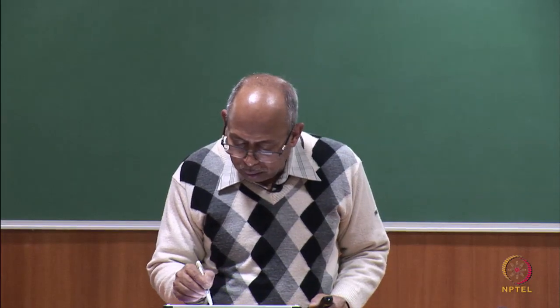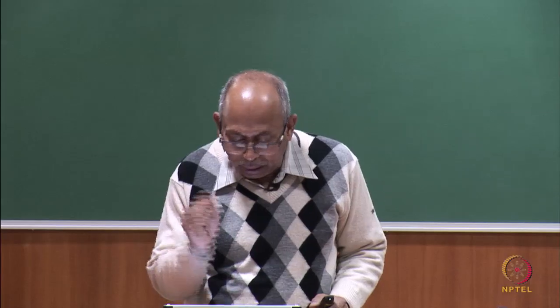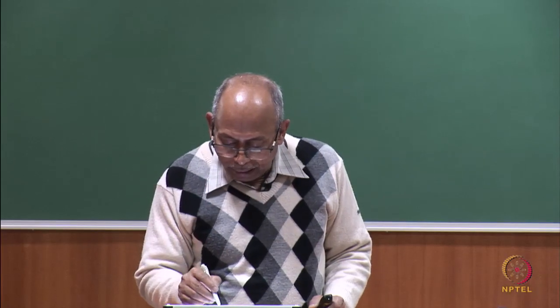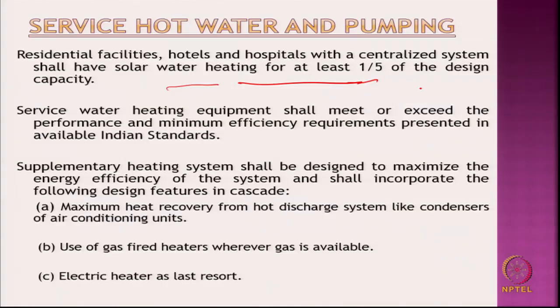So, a centralized system shall have a solar water heater, at least 1/5 of the design capacity should be through solar hot water, solar. Service water heating equipment shall meet and exceed the performance of the minimum requirement presented in the available Indian standard. So, heating equipment must have the efficiency as per the standard, and 1/5 must be solar heater.